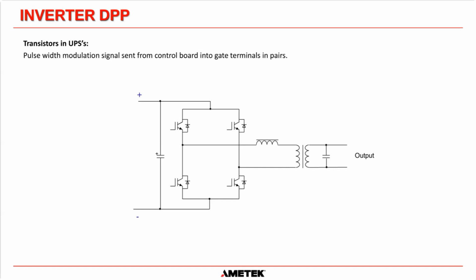So in an IGBT inverter, what we have to do is try and protect the IGBTs from blowing up by seeing high current. And in the PWM system, all of the current on a fault will be seen by the IGBTs. So we don't want that to happen. So what will happen inside a PWM inverter is it will see the high current going to that fault. It will immediately transfer the system to bypass.